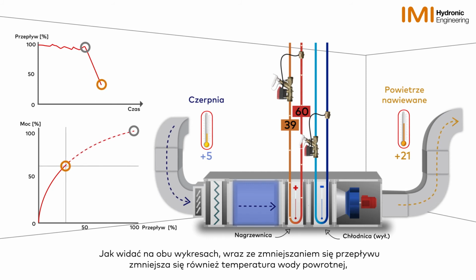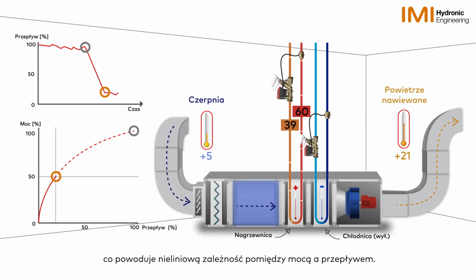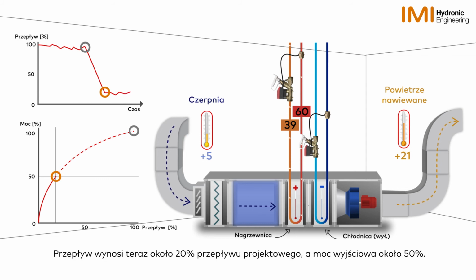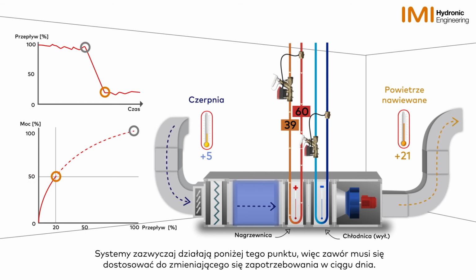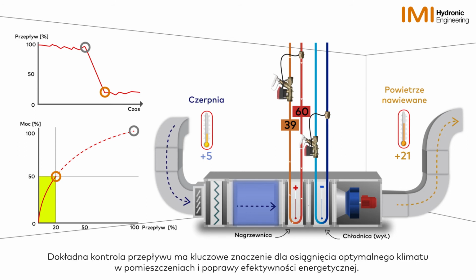As you can see in both graphs, the flow reduces, and the temperature of the return water reduces too, causing the non-linear relationship between power and flow. The flow is now at about 20% of the design flow, and power output is about 50%. Systems usually operate below this point, so the valve must adapt to changing demands throughout the day. Accurately controlling flow is critical to achieving optimal indoor climate and improving energy efficiency.